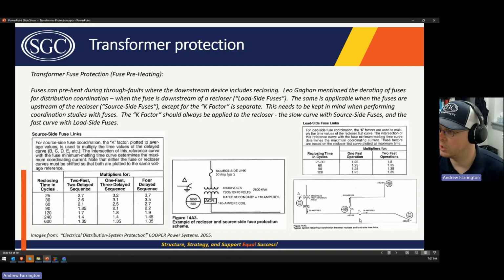So in this case, you need to apply the K factor, and it's always applied to the recloser. The slow curve gets the K factor when you have a source side fuse, which is this instance. And then the fast curve gets the K factor when you have a load side fuse. So this is what Leo talked about.